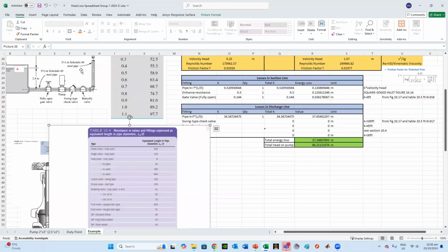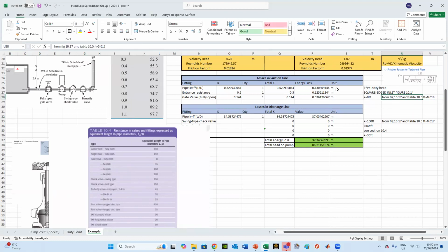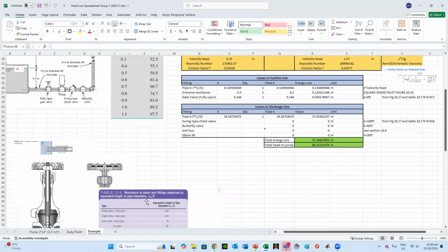Now I'm looking, and I got them in the opposite direction. Sorry for that. That should be 0.017, because it's 3.5 inches for the suction line, and this one, the discharge line, is 8. So you need to be careful with those when we read them, but it's the same concept.